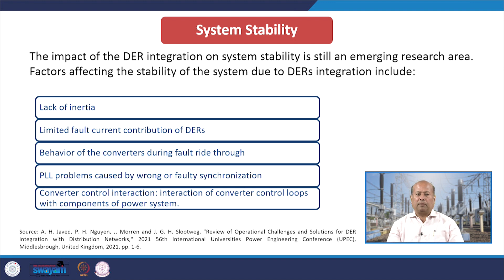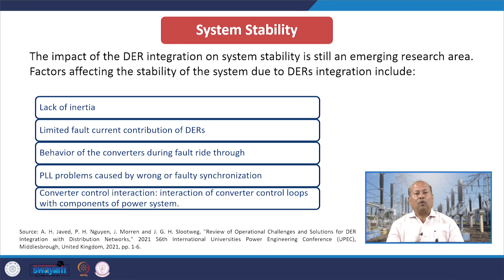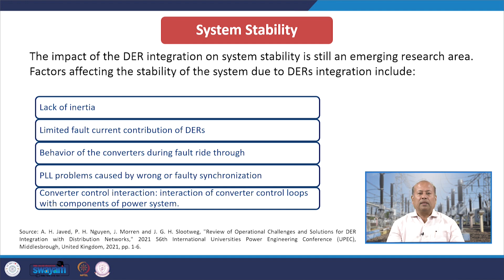Let us focus on system stability. The impact of DER integration on system stability is still an emerging research area. Factors affecting stability include lack of inertia — because rotational devices keep on reducing due to PV integration, so the inertia of the system is going to fall — limited fault current contribution of DERs, behaviour of converters during fault ride-through, PLL problems caused by wrong or faulty synchronization, and converter control interactions.